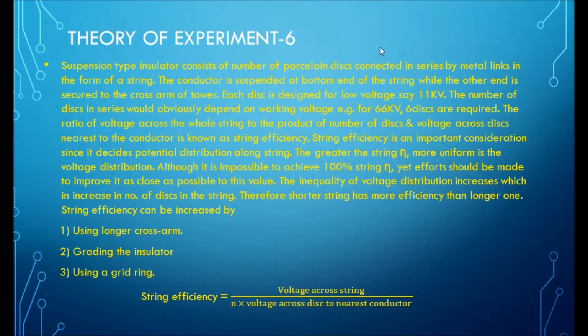This is the theory of string efficiency. How to calculate string efficiency: voltage across the string divided by N, where N is the number of discs, times the voltage across the disc nearest to the conductor. This is the string efficiency.